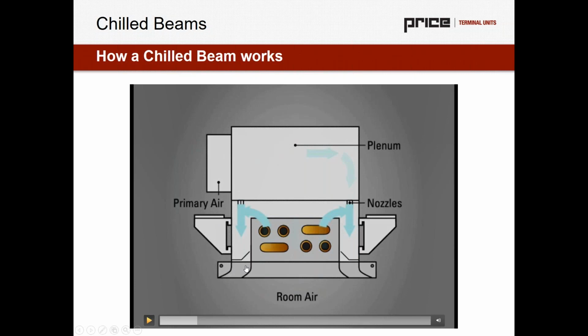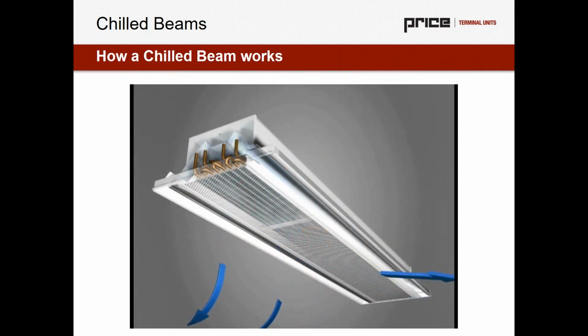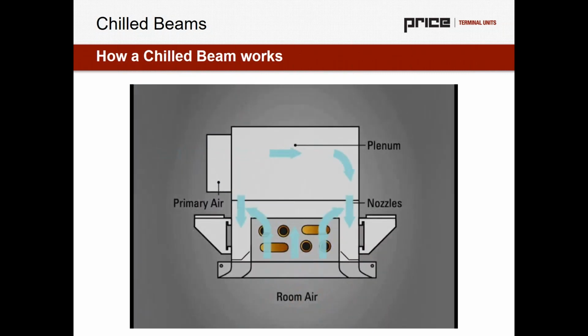So with this effect of air induction, we're generally seeing a much higher magnitude of air delivered than air supplied to the equipment. We're usually seeing somewhere definitely in the realm of 2 to 4, and sometimes even more, air discharged than air supplied, primary air that is.